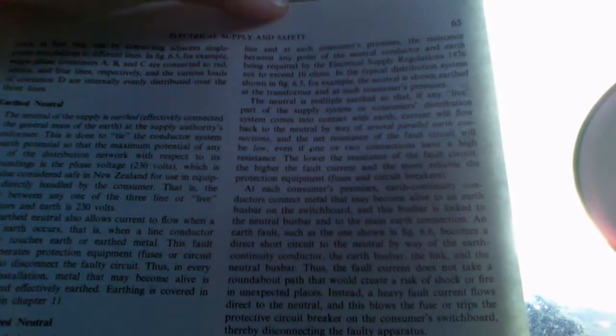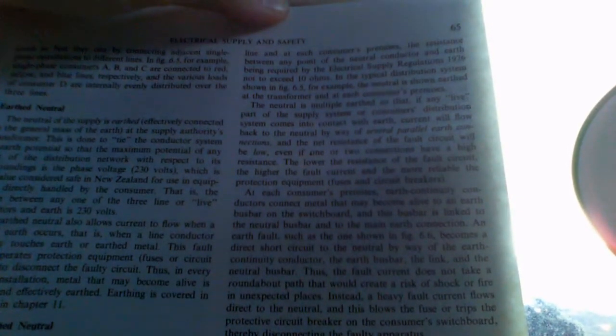In the typical distribution system shown in figure 6.5, for example, the neutral is shown earthed at the transformer and at each consumer's premises. The neutral is multiply earthed so that if any live part of the supply system or consumer's distribution systems comes into contact with the Earth, the current will flow back into the neutral by way of several parallel earth connections, and the net resistance of the fault circuit will be low. Even if one or two connections have a high resistance, the lower the resistance of the fault circuit, the higher the fault current, and the more reliable the protection equipment, fuses and circuit breakers.